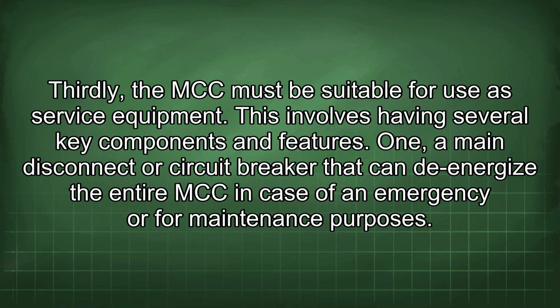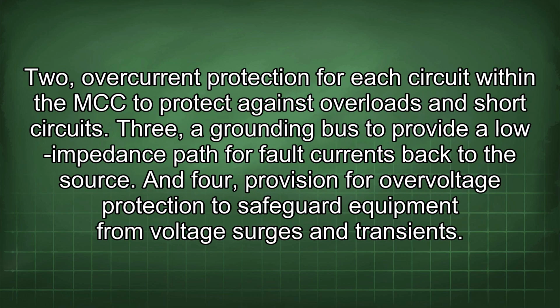1. A main disconnect or circuit breaker that can de-energize the entire MCC in case of an emergency or for maintenance purposes. 2. Overcurrent protection for each circuit within the MCC to protect against overloads and short circuits. 3. A grounding bus to provide a low impedance path for fault currents back to the source. And 4. Provision for overvoltage protection to safeguard equipment from voltage surges and transients.